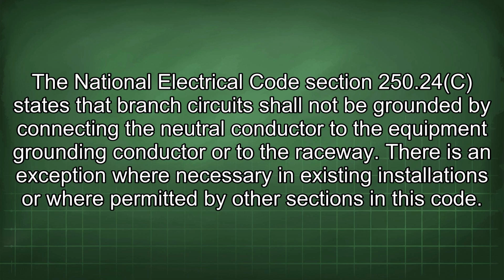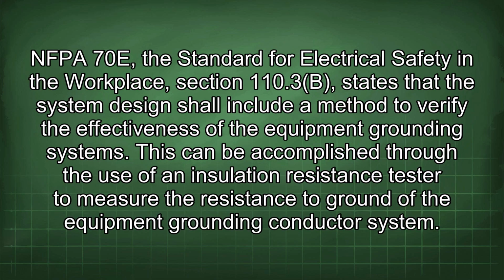The National Electrical Code Section 250.24(C) states that branch circuits shall not be grounded by connecting the neutral conductor to the equipment grounding conductor or to the raceway. There is an exception where necessary in existing installations or where permitted by other sections in this code. NFPA 70E, the Standard for Electrical Safety in the Workplace, Section 110.3(B), states that the system design shall include a method to verify the effectiveness of the equipment grounding systems.